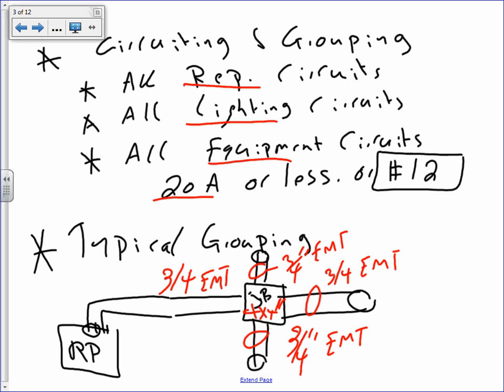The other way is, of course, you move horizontally in a conduit in a wall. Depending upon the wall, like this one, you can't move horizontally. You have to come from the top right through the cavity of these blocks and pick up the receptacles one at a time. So I showed you just typically physically how you are going to do that in the field, right? What I'm interested in here, from here down, an electrician is going to handle. From here up, always get into the habit of grouping: come with a 3/4 of an inch, or an inch sometimes, and group the circuits inside it. You're going to know why I picked the 3/4 of an inch in a second.